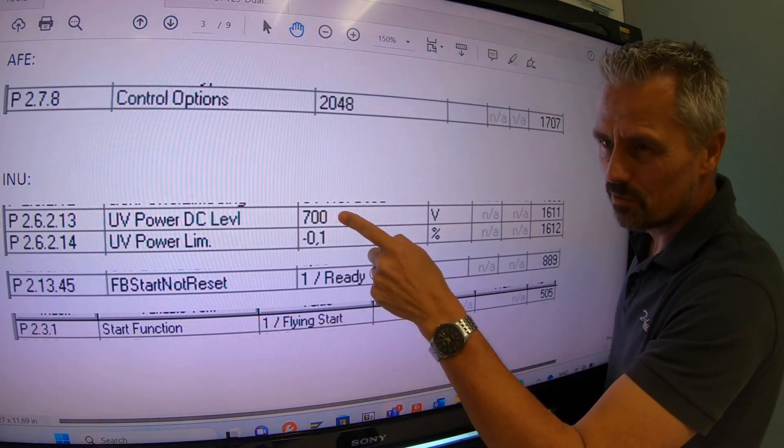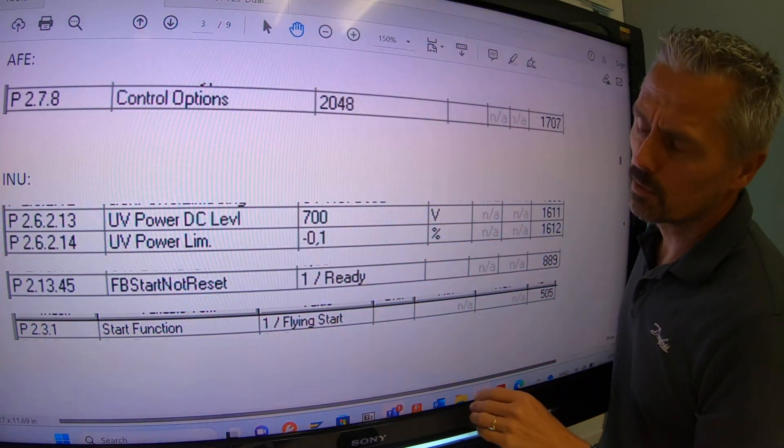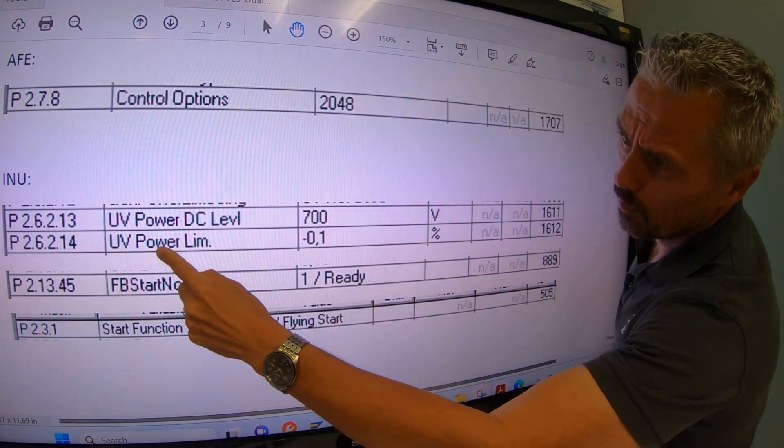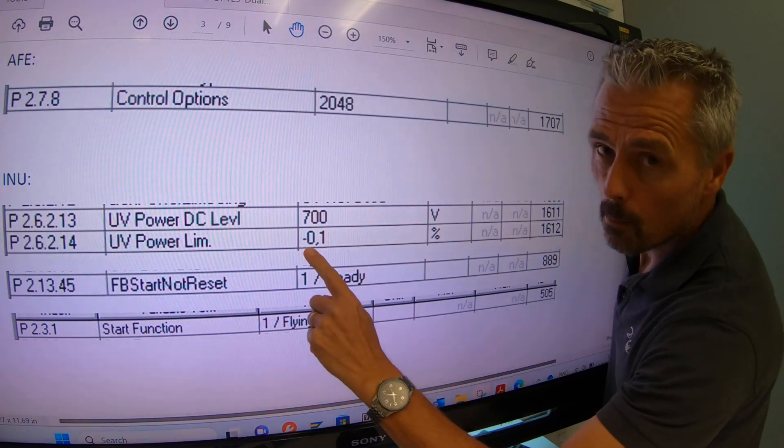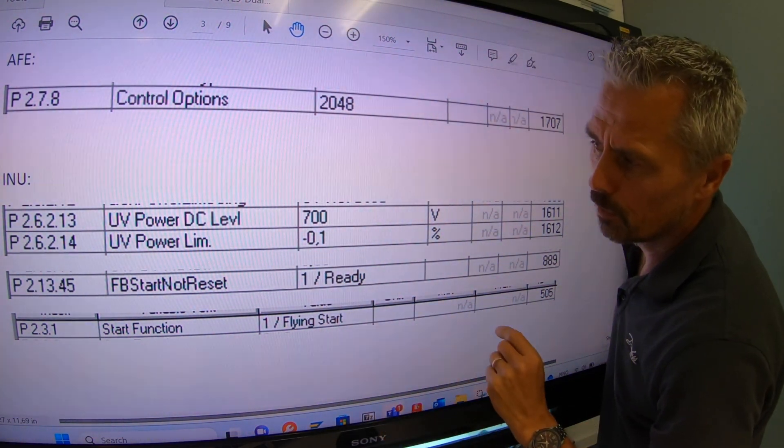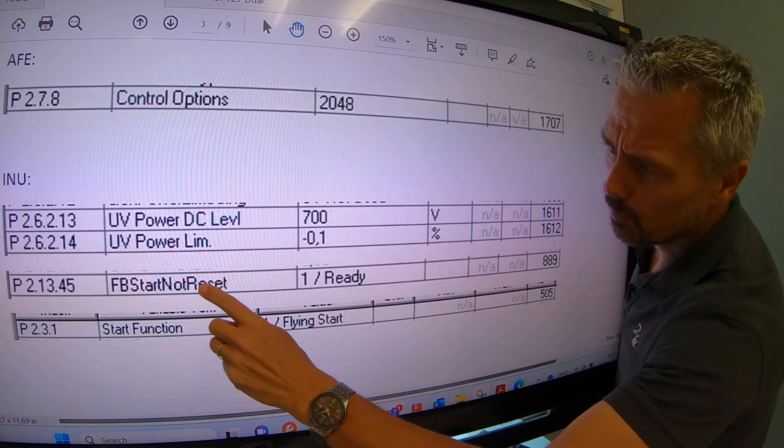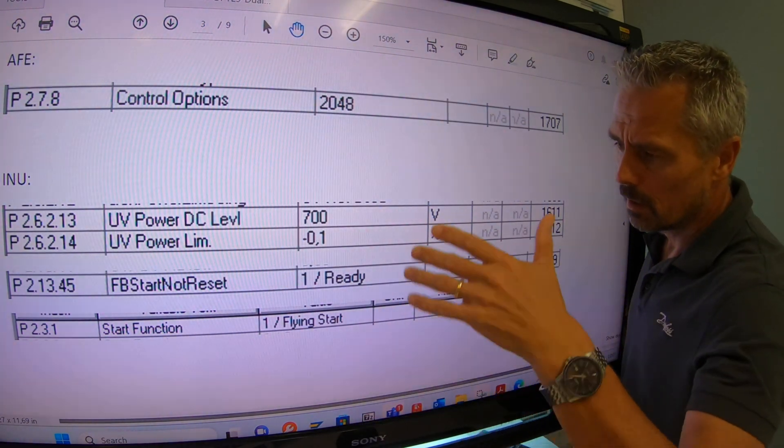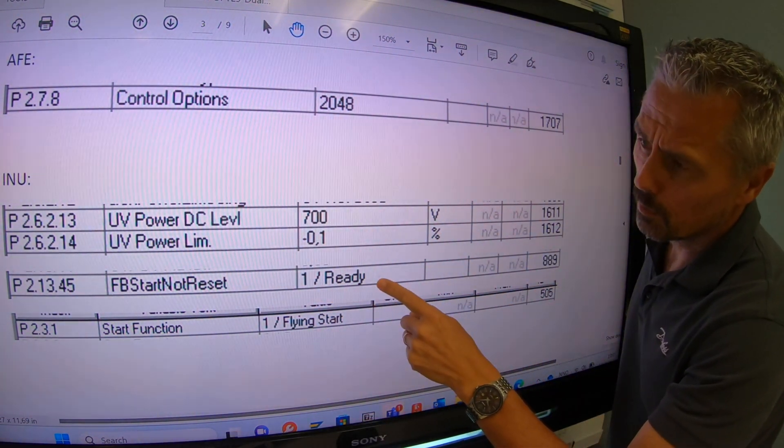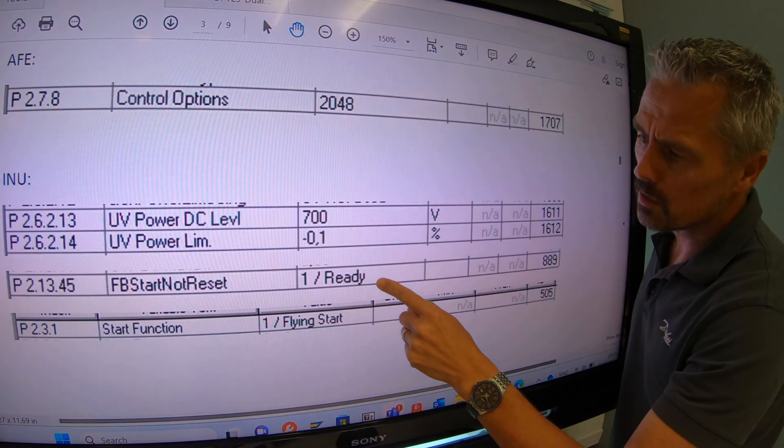In our testing, we are going to put it to 650 because then the curve is a little bit more clear. Activate it by UV power limit. Set it to minus 0.1. Also the field bus startup, put it to 1 ready because then it will restart automatically.